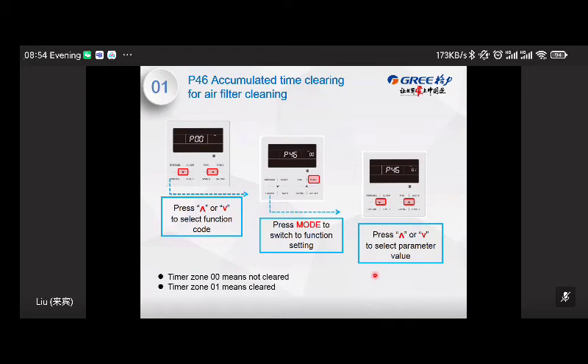Next one, P46, accumulated time clearing for the filter. You know, for the VRF wired controller, you can set the filter reminder, right? Because at the beginning, you install the duct or the cassette. However, after long time running, the filter may be dirty, may be jammed, and cause some air conditioning performance problem. So at the beginning, you can set the reminder time. And then after the time reached, there will be a clean icon display and blink on the wire controller to remind you to clean the filter.